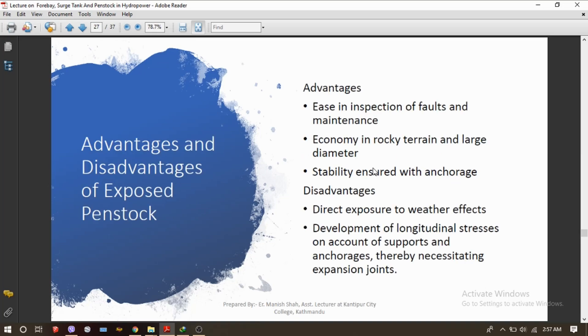Coming to the advantages and disadvantages of exposed penstock: since it is exposed, it is very easy to carry out inspection and maintenance. It is very economical in rocky terrain and for large diameter pipes, and stability is ensured with anchorage or anchor blocks. The disadvantages are that it has direct exposure to weather effects and develops longitudinal stress on account of supports and anchorage, thereby necessitating expansion joints.